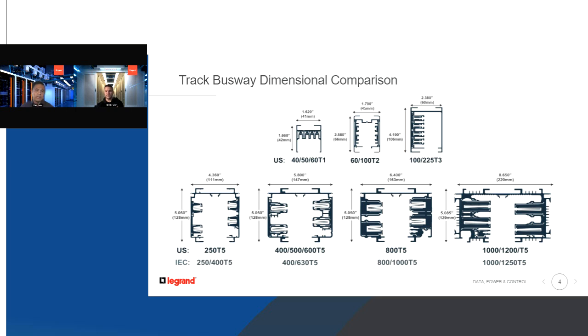Within the T5 family, you can actually use the same type of plug-in module, whether it's the 250 amp, 800 amp, or 1200 amp. The reason I mention that is it helps future-proof your data center design - if you use a 250 amp for your original design, and then 10 years later want to upgrade or add more 250s, you can still reuse the same plugins originally purchased with the busway from the inception of the design. So it's very flexible in that way.